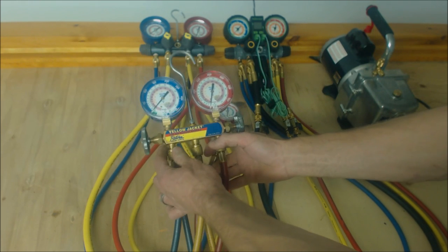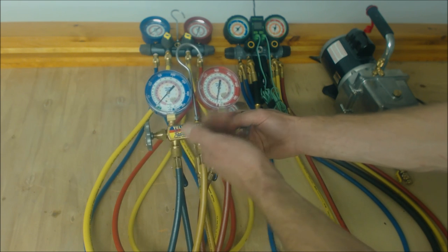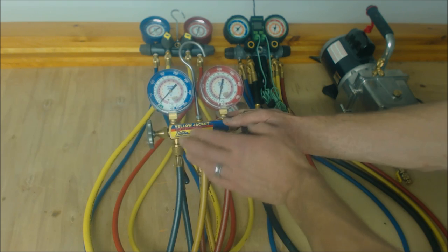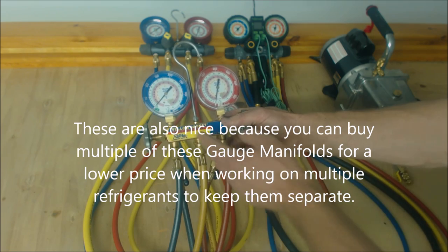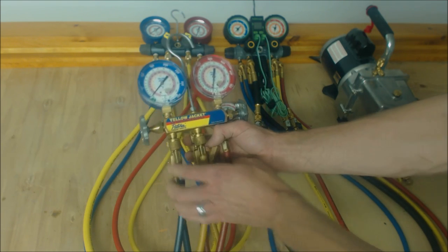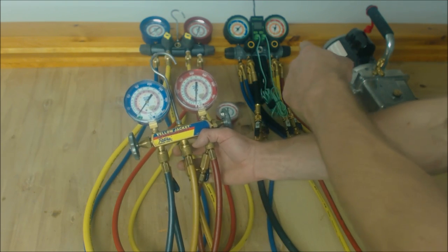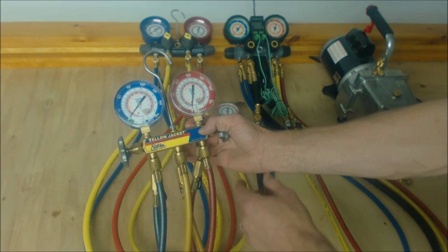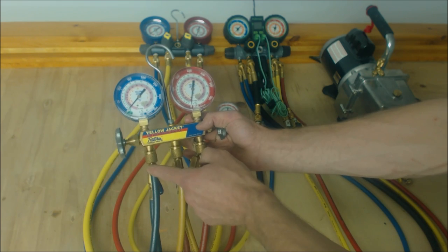They're fairly cheap. Now we can go over the two valve three port refrigeration manifold gauge set. This set would be maybe for somebody starting out. I actually have three of these or four if you're a professional doing it every day. This handle will connect your service hose to your low side. When you open that up, this handle is going to connect your service line to your liquid line.